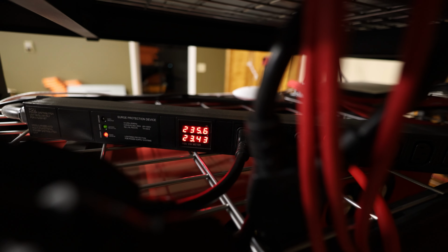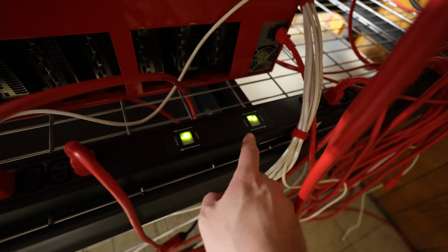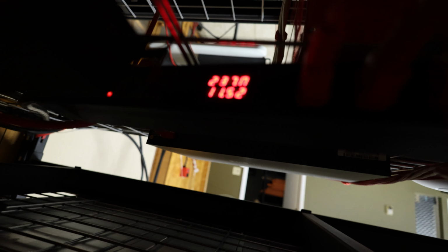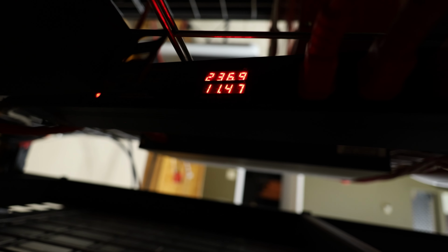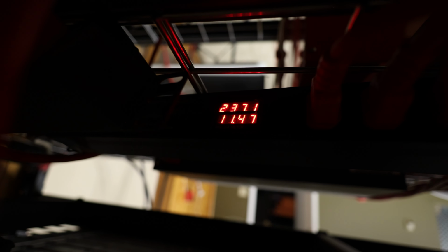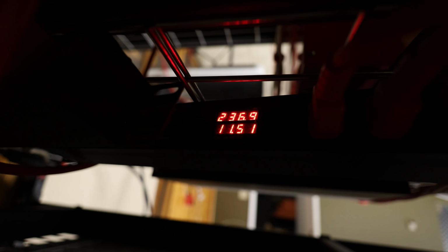So am I saturated at max capacity on power? This PDU, I'm at 23 amps. This bottom one, I am at 6 amps and 2 amps, so I'm not using much on this one. This one, you guys are gonna go upside down here, this one is at 11.4 amps, so I still have an extra 12, 13 amps I can use on this PDU, a 240 volt, 30 amp PDU. Then on this final 4th PDU, I'm using 6.66 amps at 237 volts.